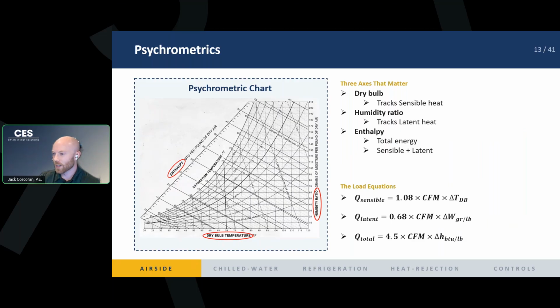It's just another way of measuring the moisture content, right? And it's just CFM and your dry bulb, and CFM and your humidity ratio. And then your last thing is your CFM and your enthalpy, right? So if you know your CFM that you required, right? Because we have our outside air CFM that was determined by code or by makeup air and mass balance. We know the CFM. If we can put it on a chart like this, we can figure out our sensible, latent, and total heat that we need in order to cool or temper it to whatever desired temperature we need. So this is a good chart if you want to look at it, and then the equations are helpful for determining your loads.